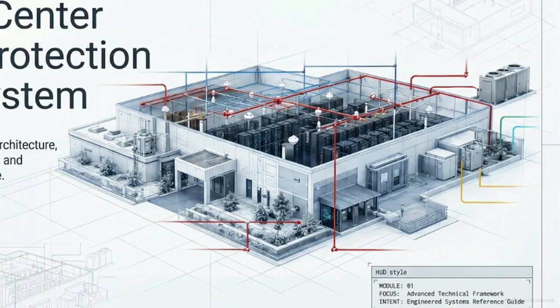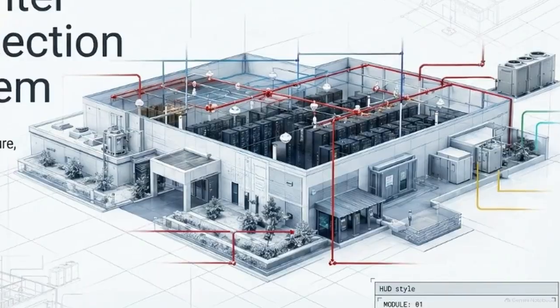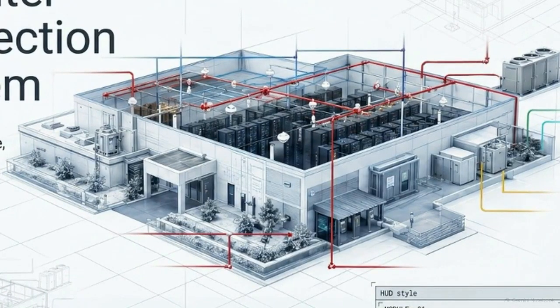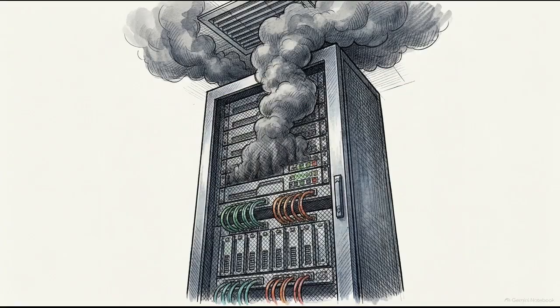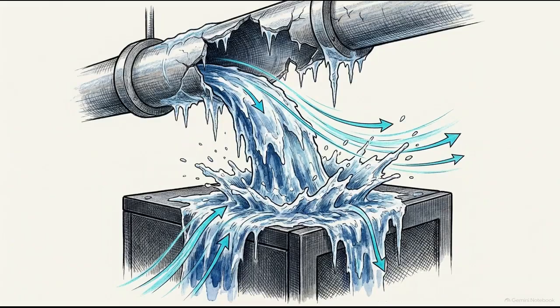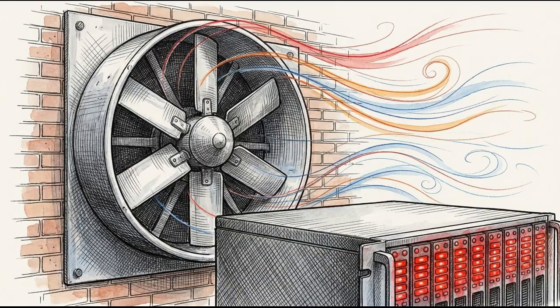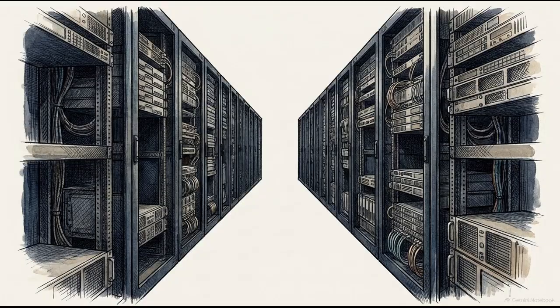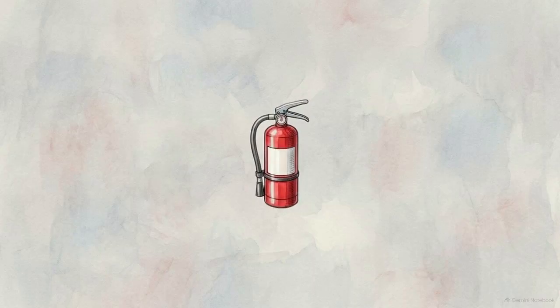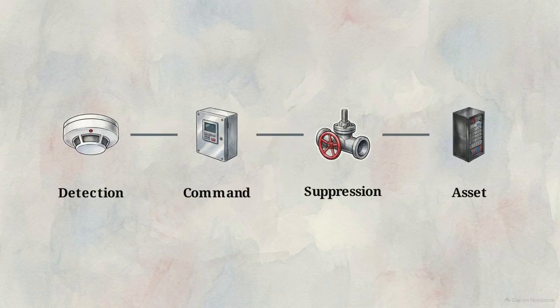The modern data center is an environment of extreme energetic density. In a facility like this, actual flame spread is only one of many catastrophic threats. Airborne smoke contamination, accidental liquid release, and the abrupt loss of cooling can destroy IT hardware as efficiently as a fire. To survive an event, data center fire protection cannot be a standalone reactive tool. It must operate as a deterministic, engineered ecosystem.